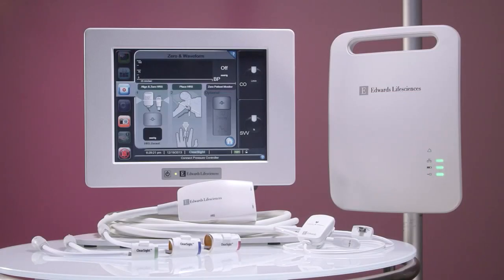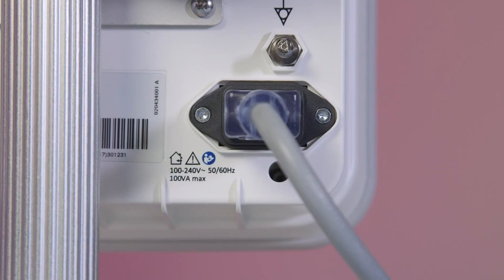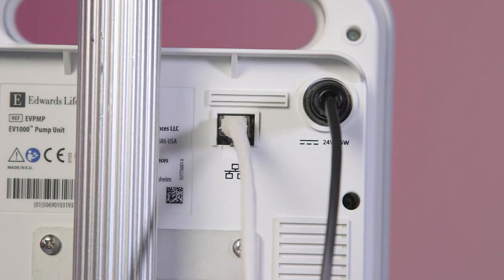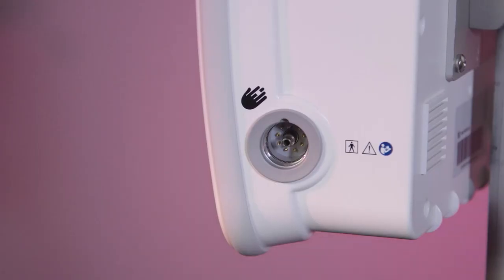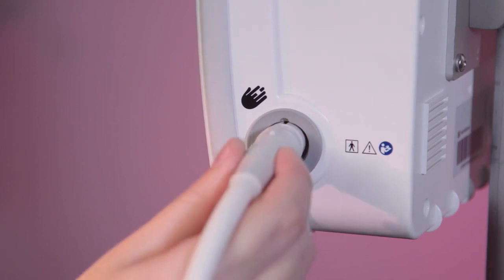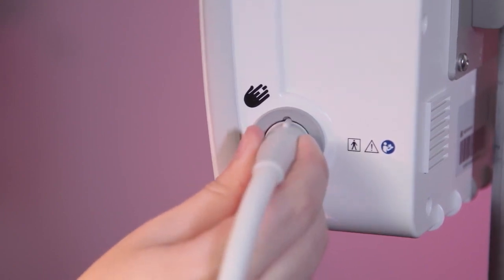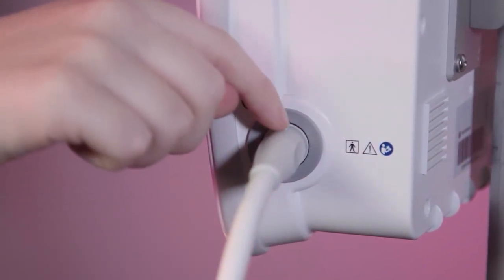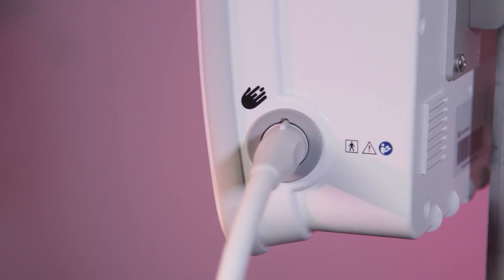The monitor and pump unit can be mounted to either a roll stand or a table stand. Confirm that the power cords are connected to the pump unit and to the monitor. Confirm that an Ethernet cable is in place to ensure communication between the pump unit and the monitor. Once power and communication have been confirmed, retrieve the pressure controller and connect it to the side of the pump unit. The pressure controller cable will only enter the port in one orientation. The groove on the cable should be facing up.